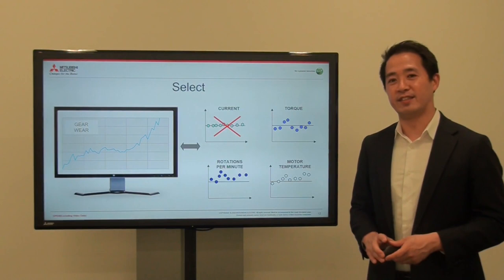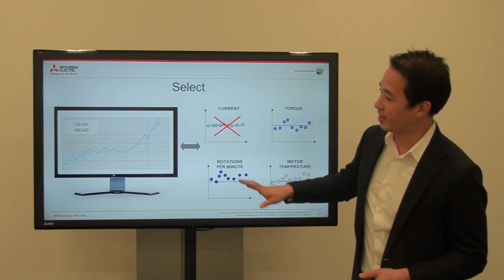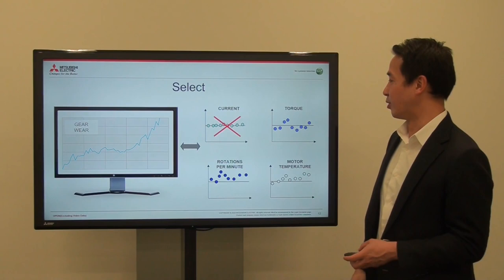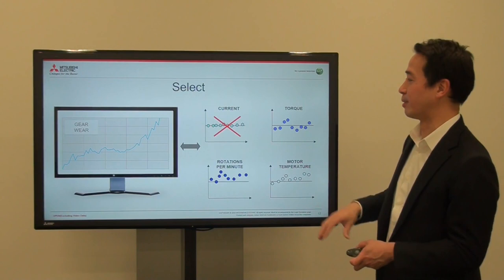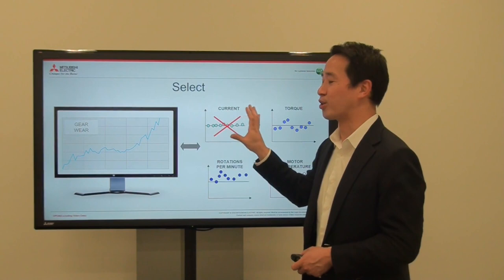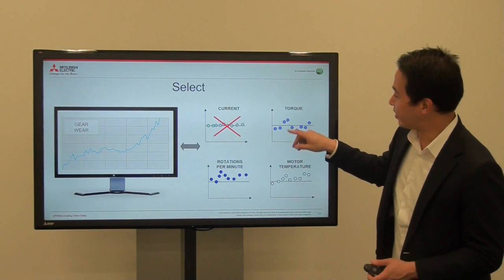The next phase is selecting the data that is relevant to the gear wear. The gear wear trend is going up over time as it wears down every day. If you look at the other data you have — for instance around the motor — you see the current, the torque, the rotations per minute, and the motor temperature. For instance, if the current is a straight line while gear wear is moving, the current probably has nothing to do with the gear wear.